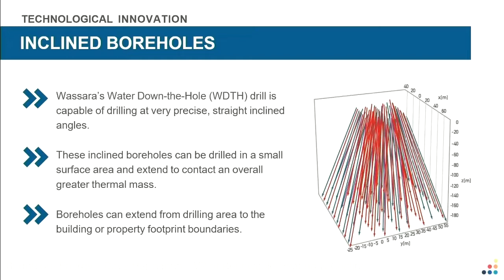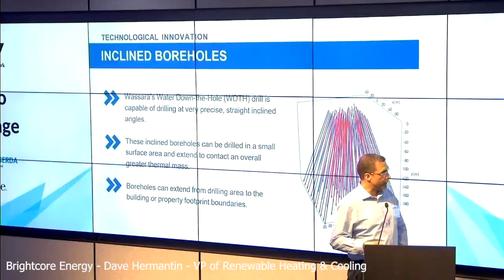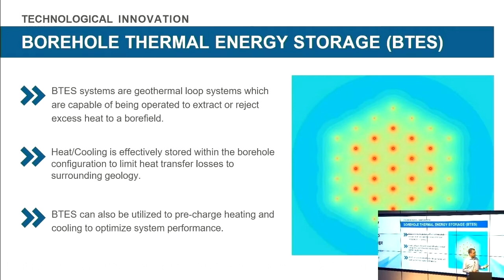So they went down from grade to about 650 feet, and they stayed on the property. The drilling is very accurate, and we can survey it. It's generally as accurate as 1% to 2% deviation from where our terminating points are designed to be. But today we're talking about thermal energy storage. Another inherent quality of ground source systems is their ability to provide, as Paul said, thermal inertia, or act as a capacitor that can buffer the loads of a building. And in a sense, this does qualify as thermal energy storage if you're using these systems to offset upcoming loads.